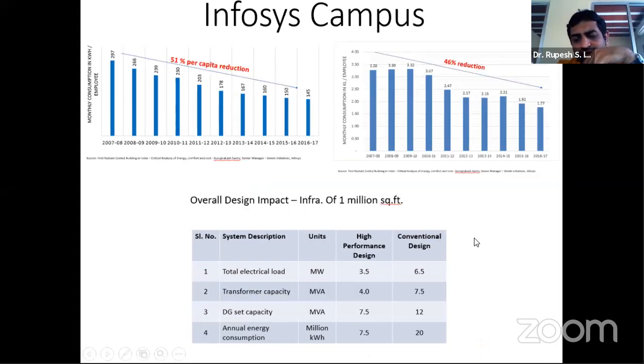I think for Infosys it was useful because they run their own buildings, and on 1 million square feet of infrastructure, the conventional electrical design was 6.5 megawatt. It came down to about 3.5 megawatt. Transformer capacity reduced again from 7.5 to 4. DG in turn again coming down. And the annual energy consumption came down from 20 million units to about 7.5 million units. So overall, the change in about 10 years was a 51% per capita reduction on the energy side and 46% on the water consumption side. Water consumption came down from 3.2 to 1.7 KL per employee. So that's per employee.